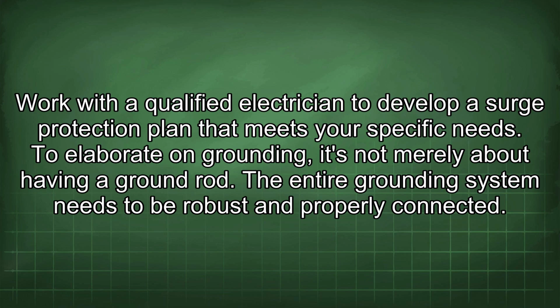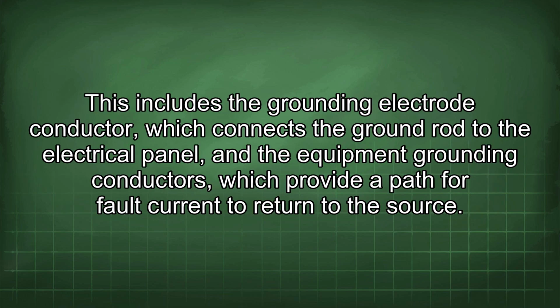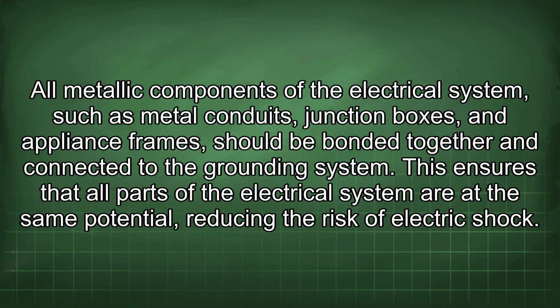To elaborate on grounding, it's not merely about having a ground rod. The entire grounding system needs to be robust and properly connected. This includes the grounding electrode conductor, which connects the ground rod to the electrical panel, and the equipment grounding conductors, which provide a path for fault current to return to the source. All metallic components of the electrical system, such as metal conduits, junction boxes, and appliance frames, should be bonded together and connected to the grounding system. This ensures that all parts of the electrical system are at the same potential, reducing the risk of electric shock.